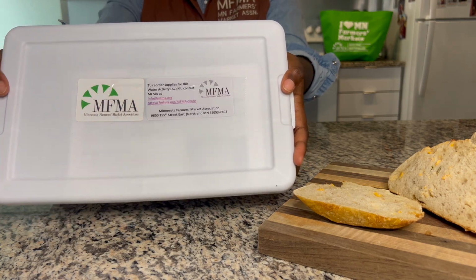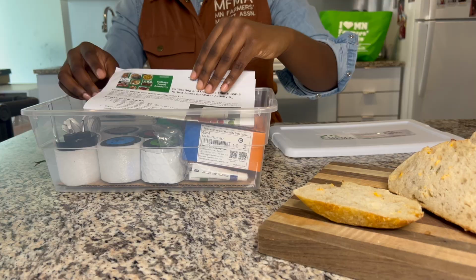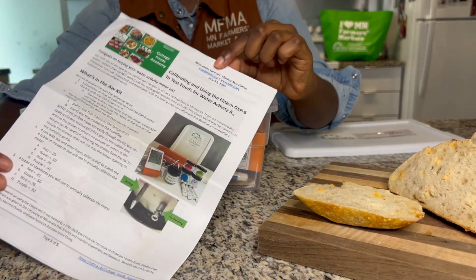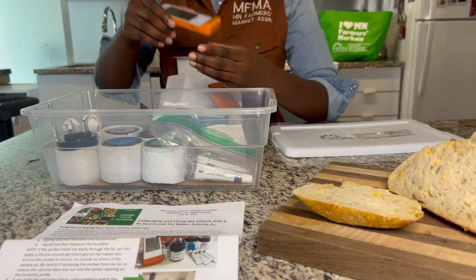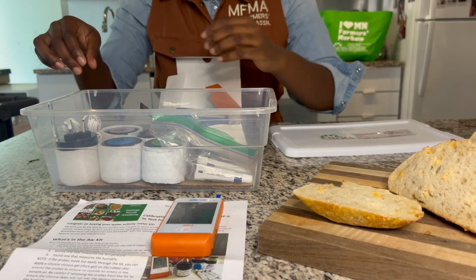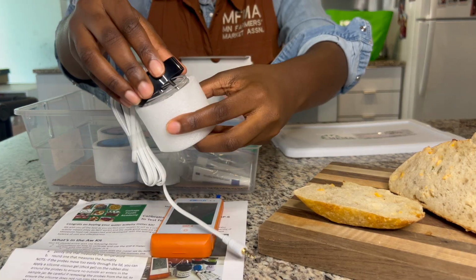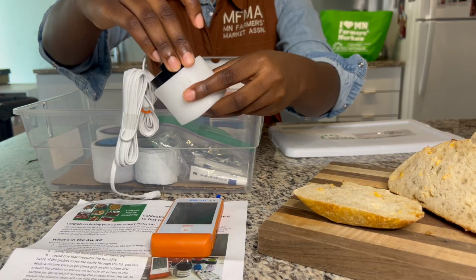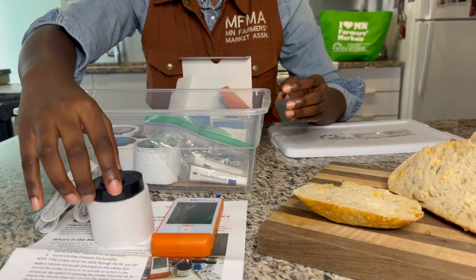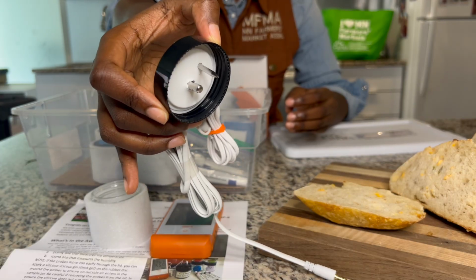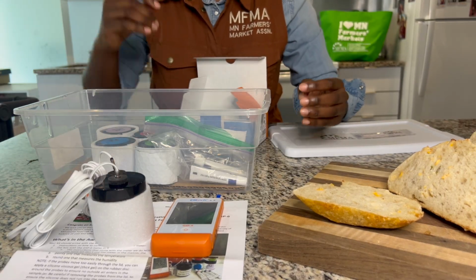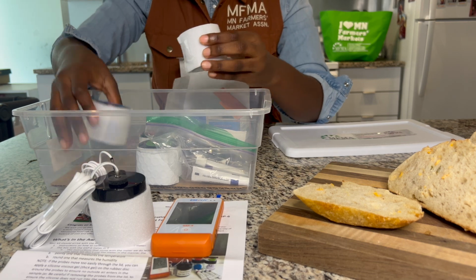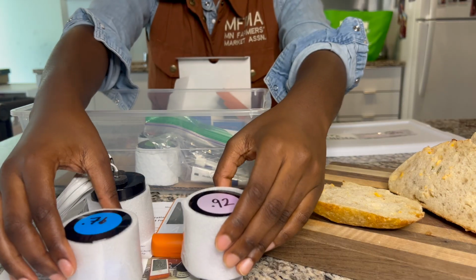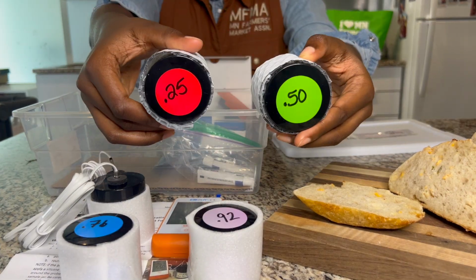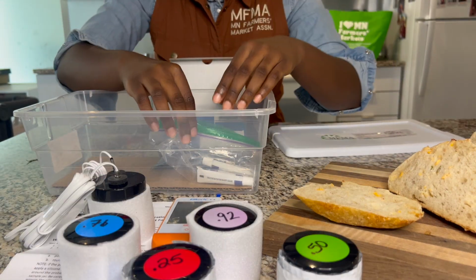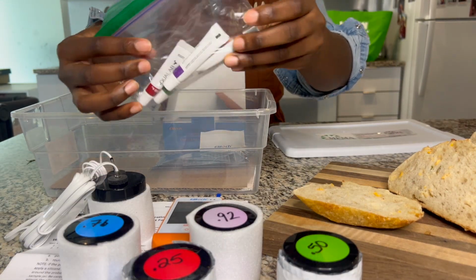What's in the kit? When your kit arrives, you should find the following items: the printed instruction guide, the GSP-6 water activity meter, a food sample jar with a lid and a liner that includes 2 probes from the GSP-6 meter. The thin probe in the food sample jar measures temperature. The rounder probe with the open slot measures relative humidity. 4 empty jars with lids and liners color-coded red, green, blue, and purple for the 4 different calibration solutions. 4 matching tubes of calibration solution.